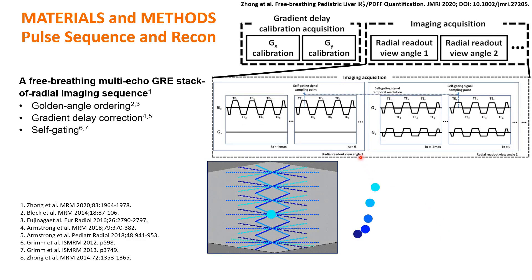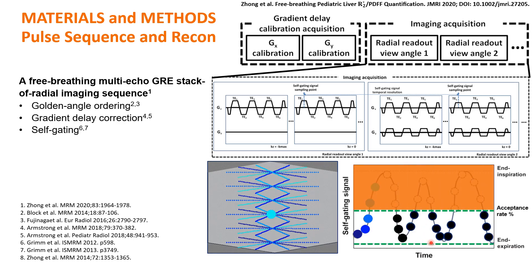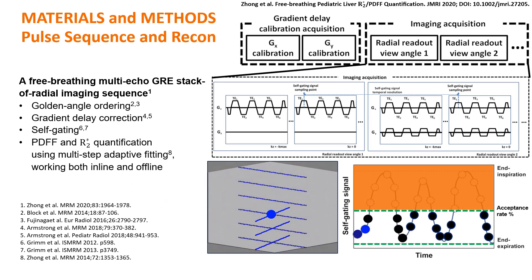The imaging acquisition module contains the self-gating signal sampling inherently. As shown in the illustration, when the K-space data sampling crosses the K-space origin, the data at the origin is sampled to form the self-gating profile. We can then apply an acceptance window to select K-space data acquired near end expiration to reconstruct the radial images. The PDFF and R2-star maps are then calculated using a multi-step adaptive fitting technique.